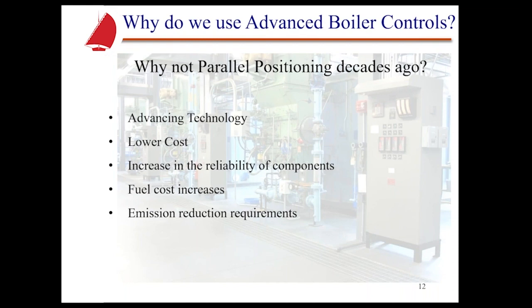Obviously, decades ago, only the largest burners would actually get a fully metered and cross-limited type system. But with parallel positioning, with the advance of technology, we were able to put it on smaller and smaller burners and gain that precise control. Another part of it is also the reliability of the components. And we can thank the automotive industry to a certain extent for this, because so much of the automobiles these days are using stepper motors, they're using servo type motors, if you will, to control different things in the automobile. So this is where a lot of this has been realized.